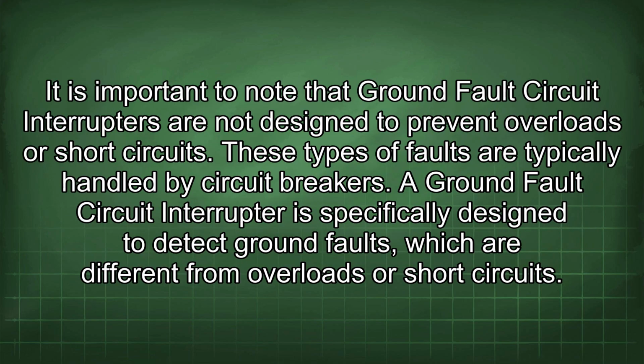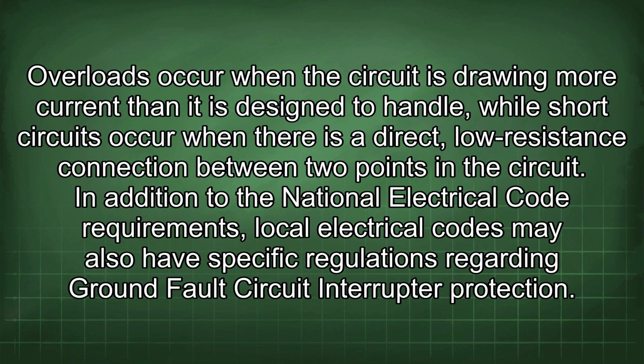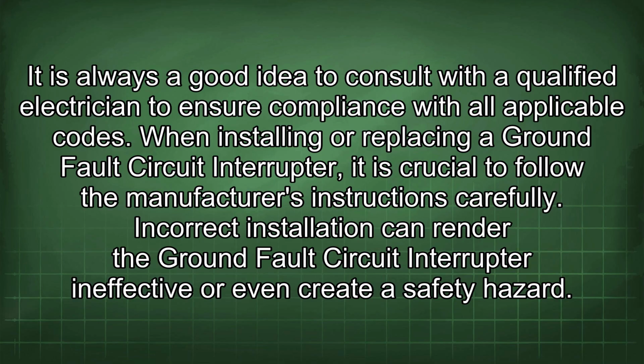It is important to note that ground fault circuit interrupters are not designed to prevent overloads or short circuits. These types of faults are typically handled by circuit breakers. A ground fault circuit interrupter is specifically designed to detect ground faults, which are different from overloads or short circuits. Overloads occur when the circuit is drawing more current than it is designed to handle, while short circuits occur when there is a direct, low-resistance connection between 2 points in the circuit. In addition to the National Electrical Code requirements, local electrical codes may also have specific regulations regarding ground fault circuit interrupter protection. It is always a good idea to consult with a qualified electrician to ensure compliance with all applicable codes.